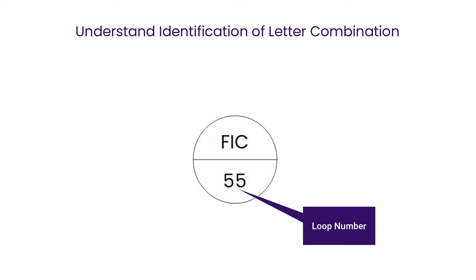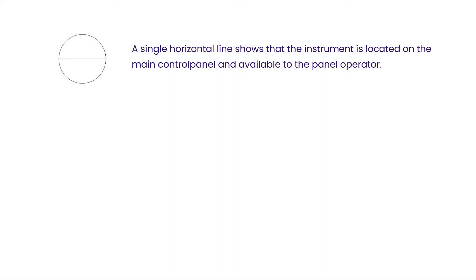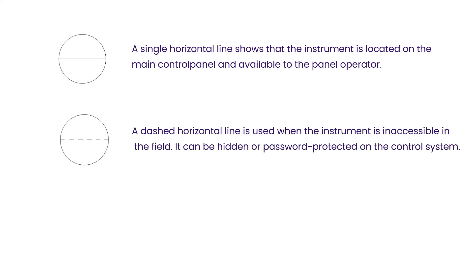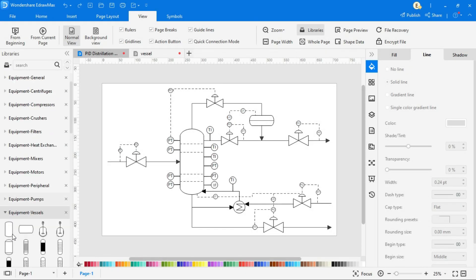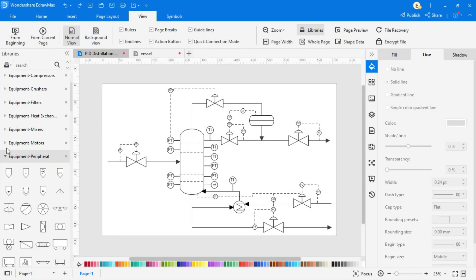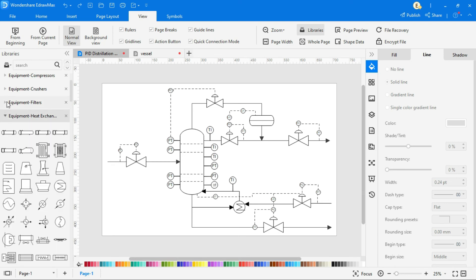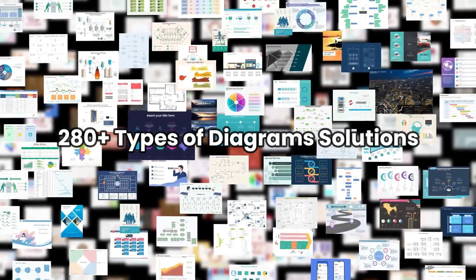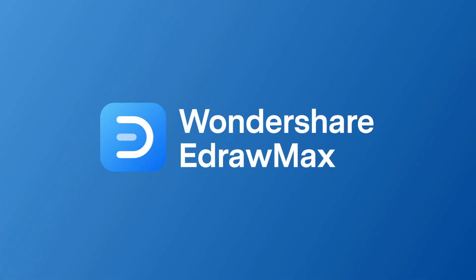A direct line denotes an instrument located on the main control panel and available for the panel operator. A dashed line denotes a behind-control-panel remote location. No line means it is a field mounted instrument accessible for the operator. We can find all kinds of PID symbols in the EdrawMax symbols library. Please find the link in the description below to try EdrawMax online or download the software. Thanks for watching and don't forget to subscribe to our channel for more videos.